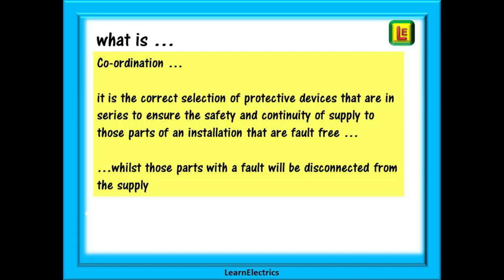And coordination is the correct selection of protective devices that are cascaded or in series to ensure the safety and continuity of supply to those parts of an installation that are fault-free whilst those parts with a fault will be disconnected from the supply. Let's be honest, selectivity and coordination have pretty much the same objective.